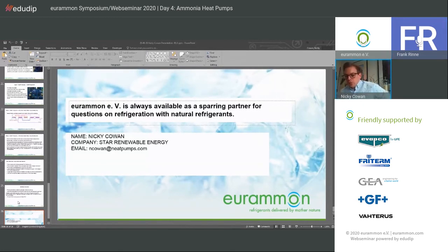Yeah, obviously, Gerd's pretty responsible though as well. That is the most challenging bit, is the temperatures that you're told to design your heat pump on are in reality not what you're going to get, especially the higher return temperature. It's just something that you have to be thinking about from the start. How do you deal with it? Like I say, for the return temperatures onto the oil cooler for the compressor, that is the key bit. We can deal with higher temperatures coming off the heat pump. But yeah, it's all about preparing for the oil cooler. And yes, it does make the design more expensive. You might have to go up a size in your heat exchanger. You might have to have a lot more oil cooling. So it's something, like I keep saying, you have to take into consideration at the start and have these conversations with the client, because you don't want to be the one footing the bill for building the heat pump.